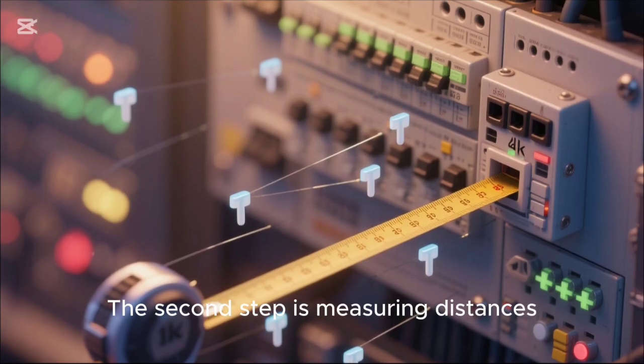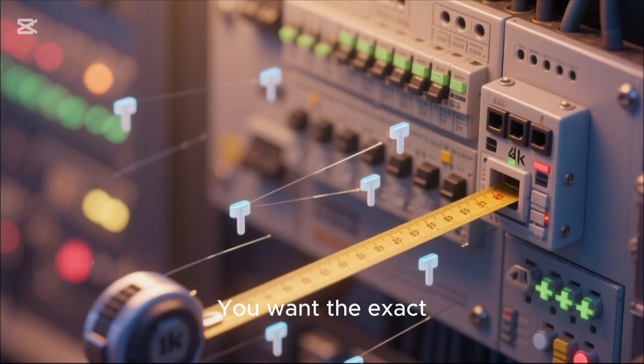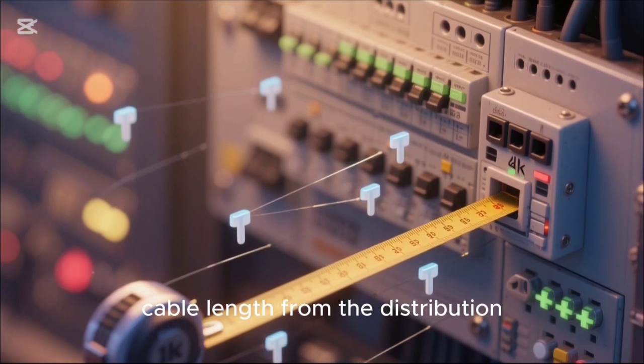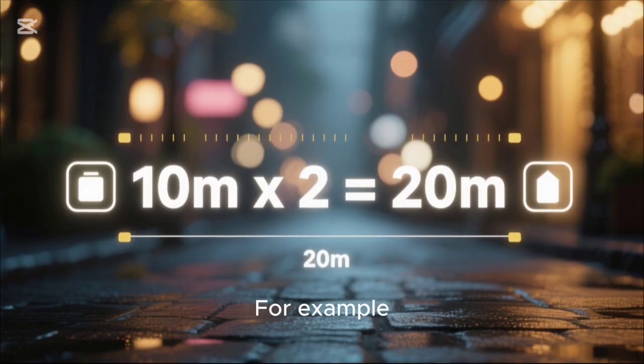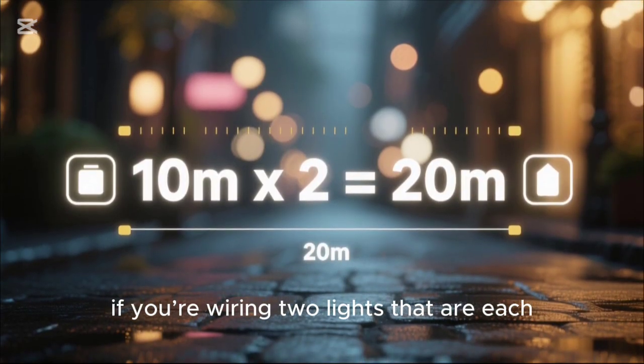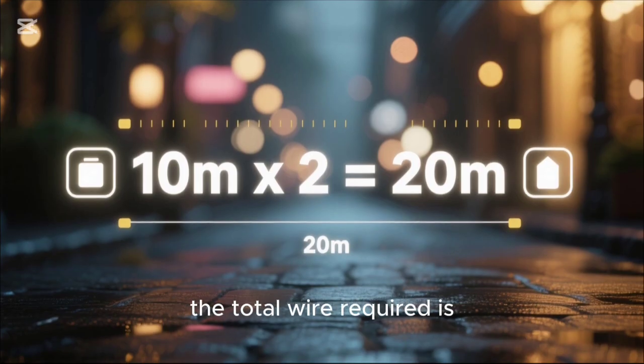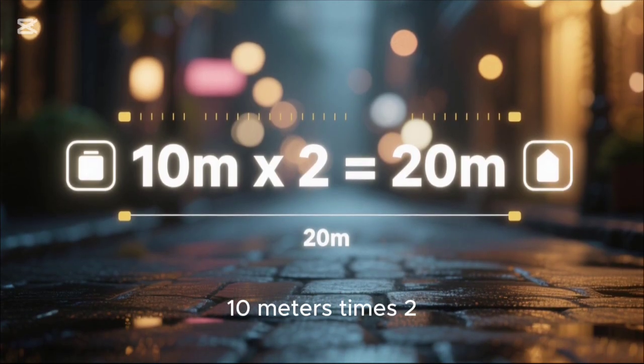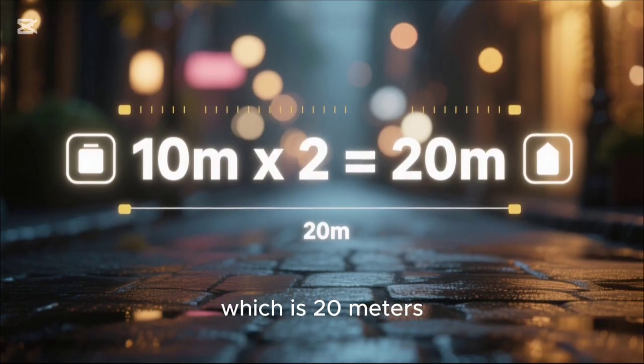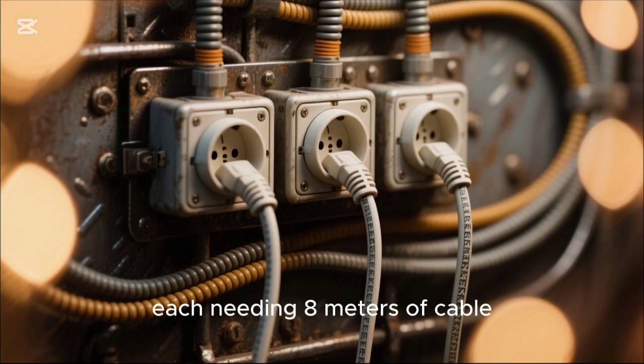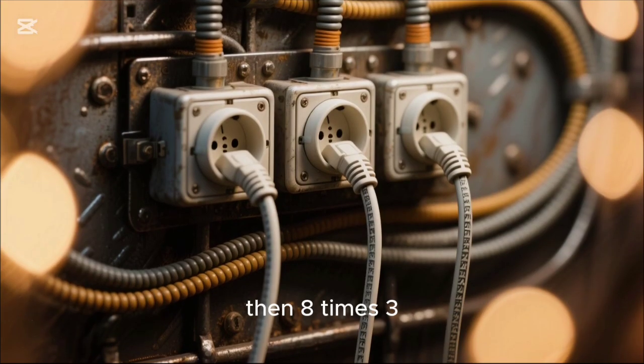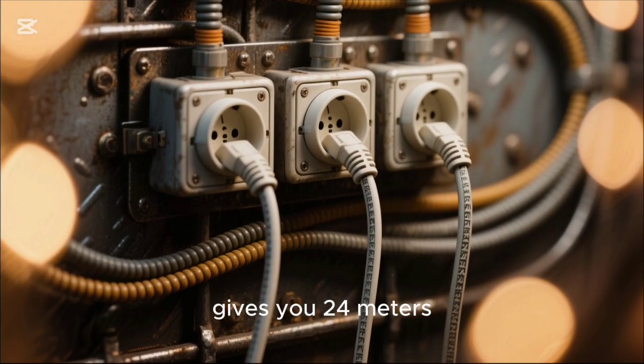The second step is measuring distances. You want the exact cable length from the distribution board to each point. For example, if you're wiring two lights that are each 10 meters away from the DP, the total wire required is 10 meters times 2, which is 20 meters. If you have 3 sockets, each needing 8 meters of cable, then 8 times 3 gives you 24 meters. This simple multiplication gives you the base cable length.